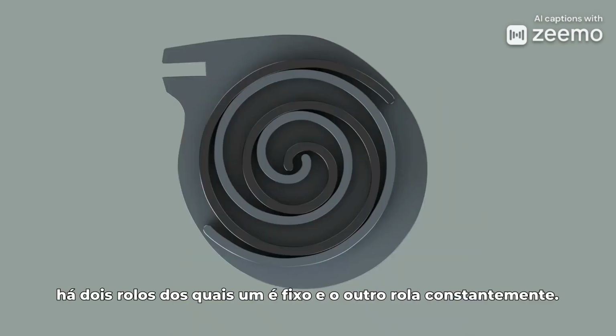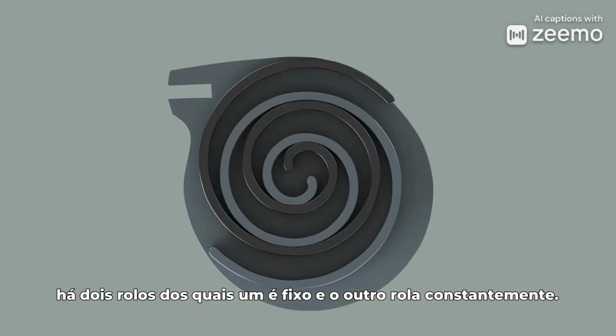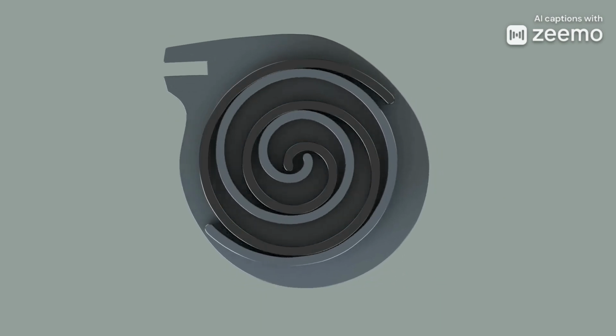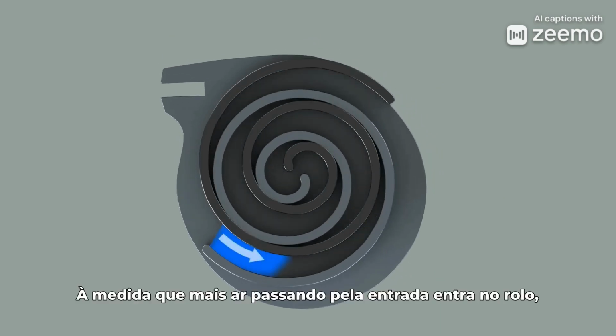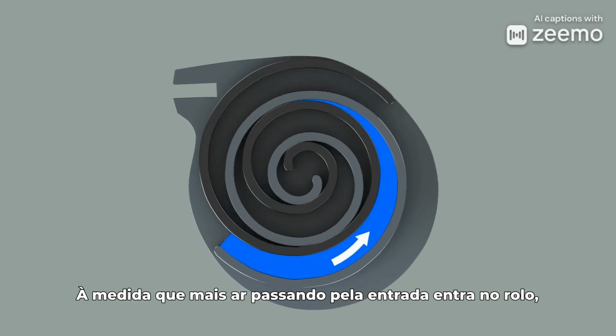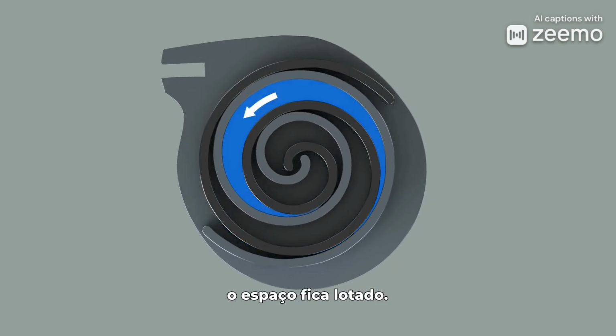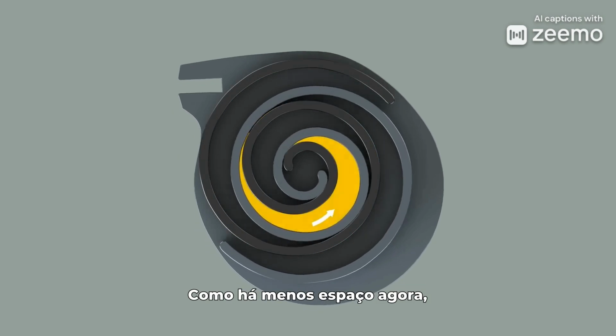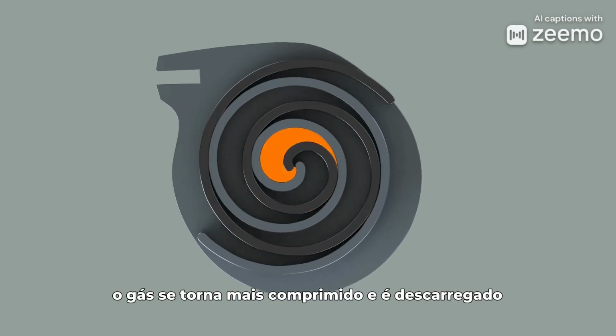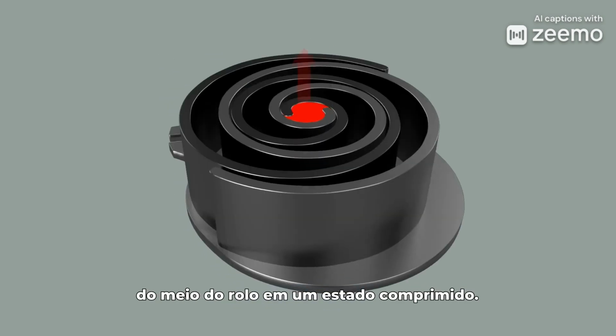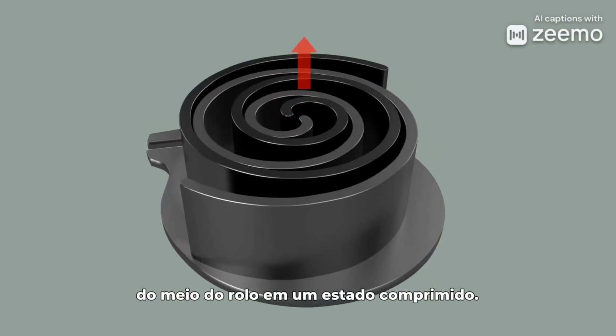In a scroll compressor, there are two scrolls, of which one is fixed and the other rolls constantly. As more air coming through the entrance gets inside the scroll, space becomes crowded. As there is less space now, gas becomes more compressed and is discharged from the middle of the scroll in a compressed state.